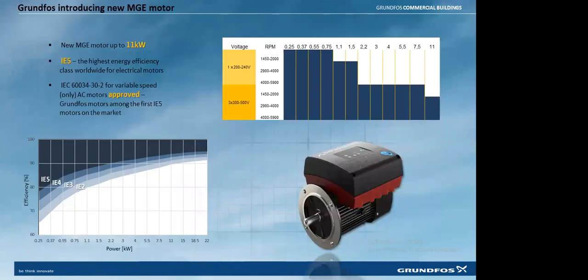The main important factor is that you will have a better partial load efficiency. At 100% load, the IE5 delivers a certain efficiency value. When it comes to 75% and 50%, without compromising on losses, we get a better efficiency compared with IE3 or IE4 motors. So that's an advantage. Here it is a permanent magnet motor.